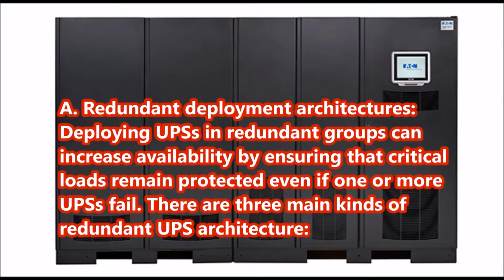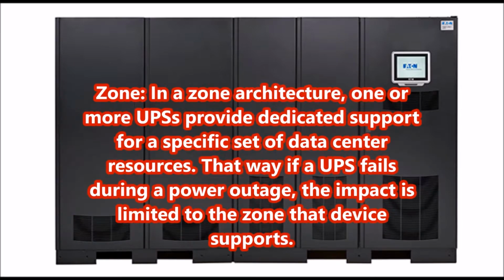Redundant deployment architectures. Deploying UPSs in redundant groups can increase availability by ensuring that critical loads remain protected even if one or more UPSs fail. There are three main kinds of redundant UPS architecture. Zone. In a zone architecture, one or more UPSs provide dedicated support for a specific set of data center resources. That way, if a UPS fails during a power outage, the impact is limited to the zone that device supports.